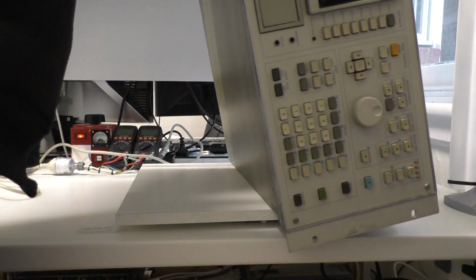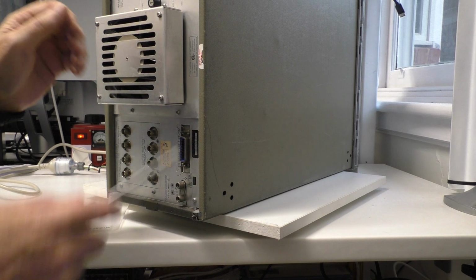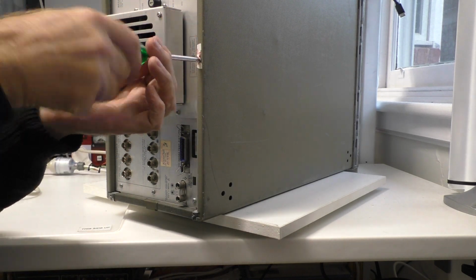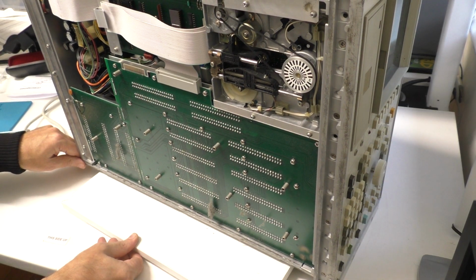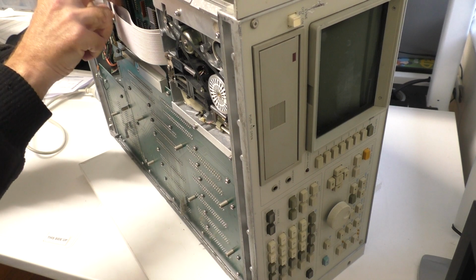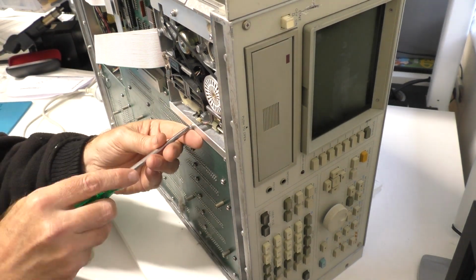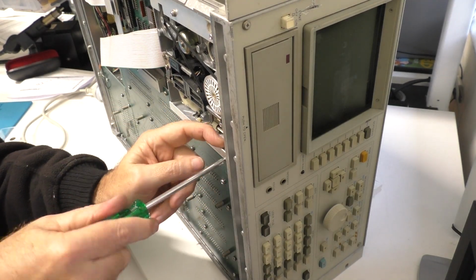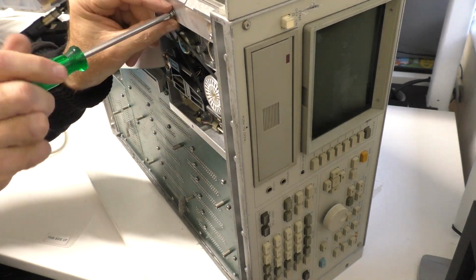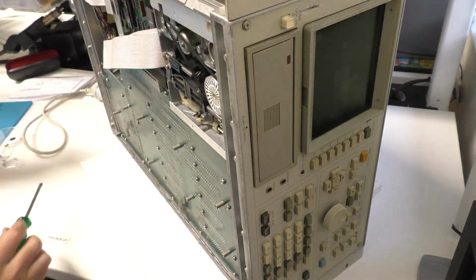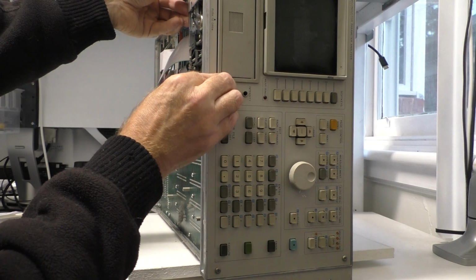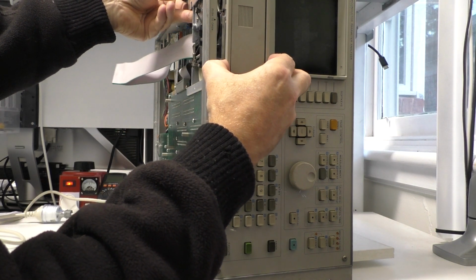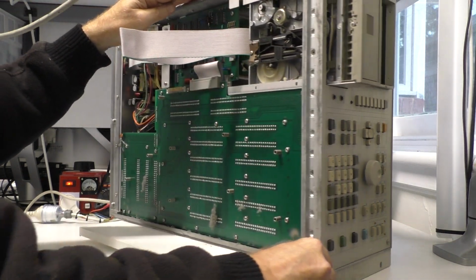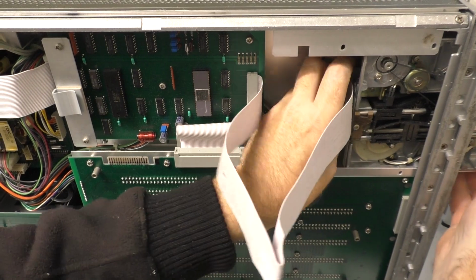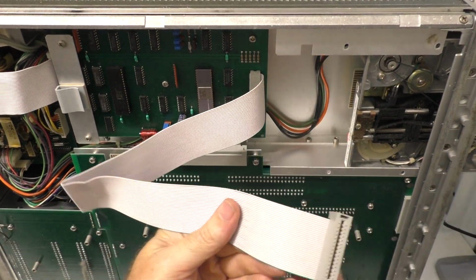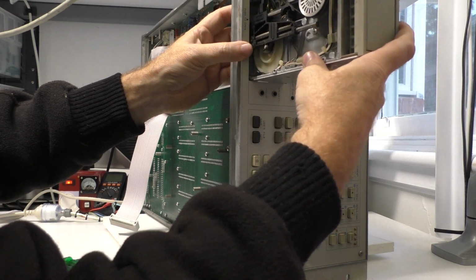Unplug the unit. Place it on its right side. Remove the bottom cover. Unlatch the ribbon cable and remove the 4 screws securing the floppy drive to the chassis. We can now gently slide the drive forward. Remove the ribbon cable from the drive. Slide the drive all the way out.